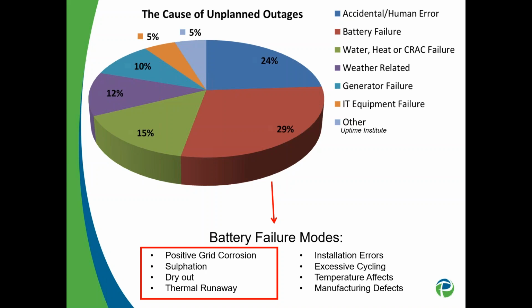The failure modes carved off to the left, highlighted in red, are positive grid corrosion, sulfation, dryout, and thermal runaway. They are heavily due to how those batteries are charged, so we're going to look at the voltage portion of it. If the voltage is too high, you get positive grid corrosion building up and causing dryout as well. If the batteries are charged too low, you get sulfation. And the result of too much dryout is thermal runaway. That's why we carved it out that way.